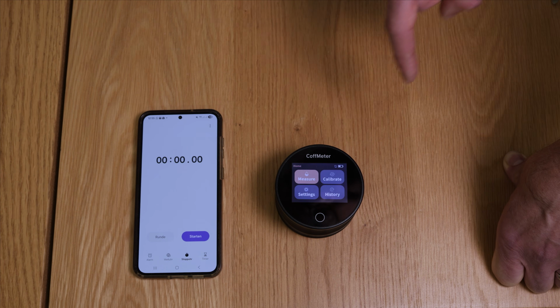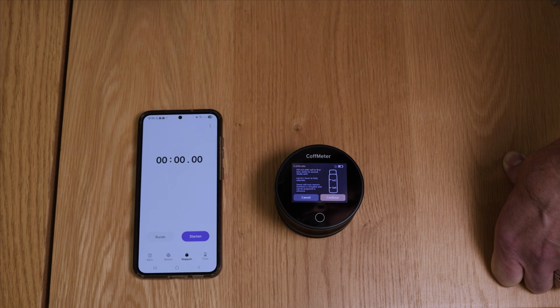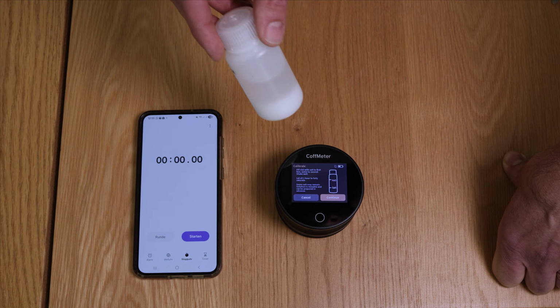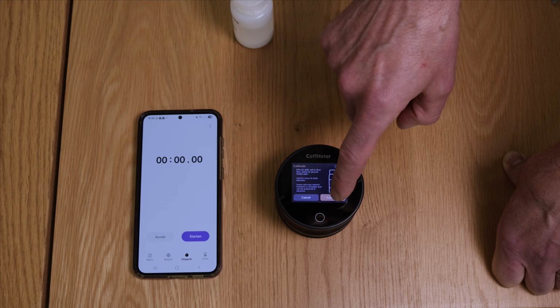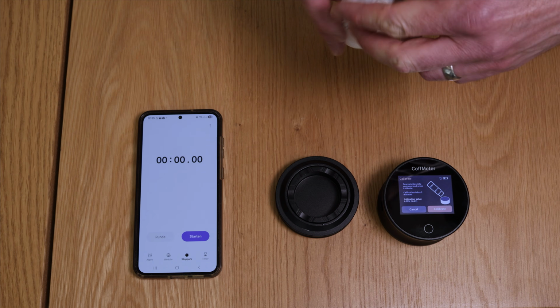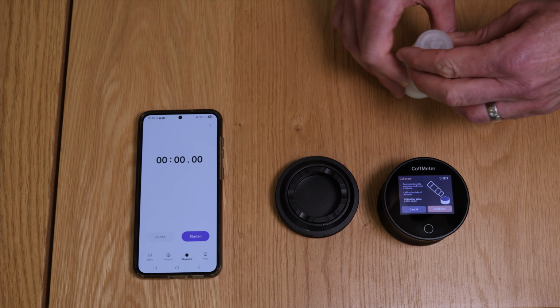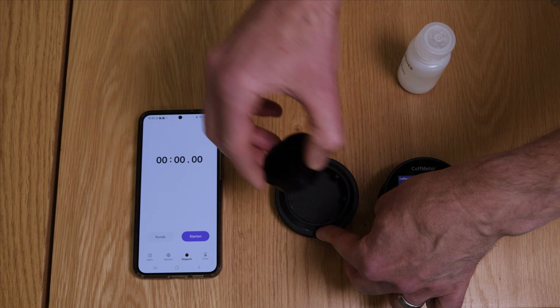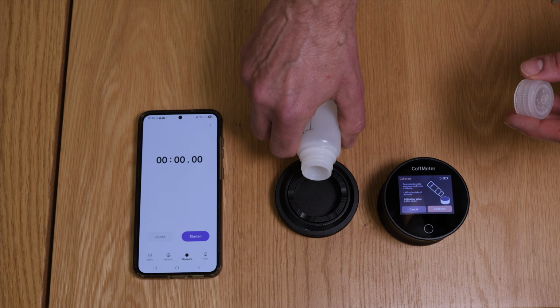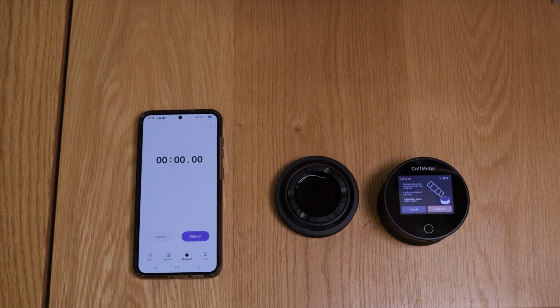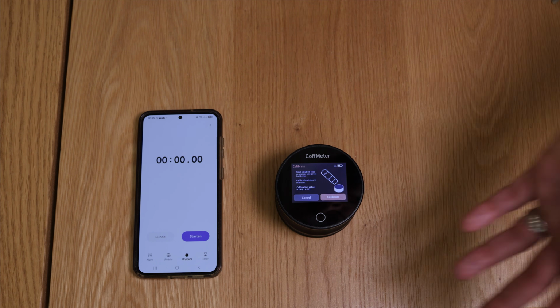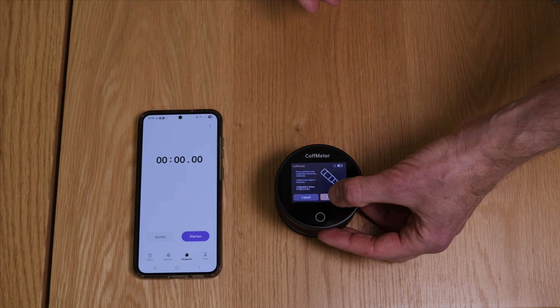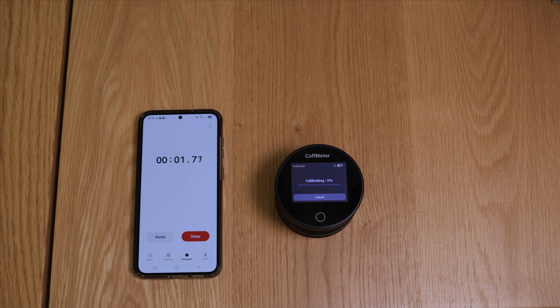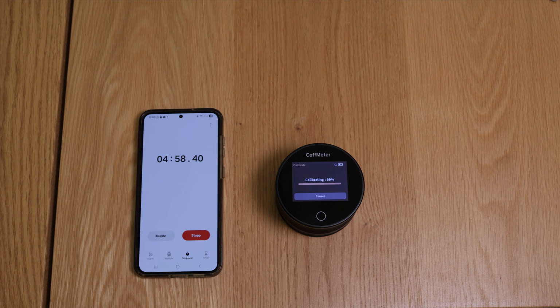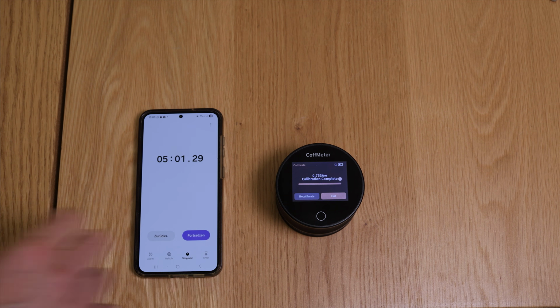Now when it comes to calibration, you do the procedure the same as with all the other water activity devices. So preparing this solution of salt and distilled water and putting it in this little sample tray. By the way, quite a nice one, you can take this out by turning it. It's a magnetic one, nicely solved by DiFluid CoffMeter. You put in the liquid, and now we are going to do a calibration and check how long this takes. So calibration took 5 minutes.